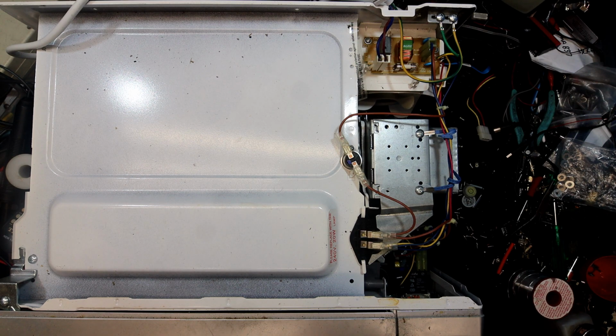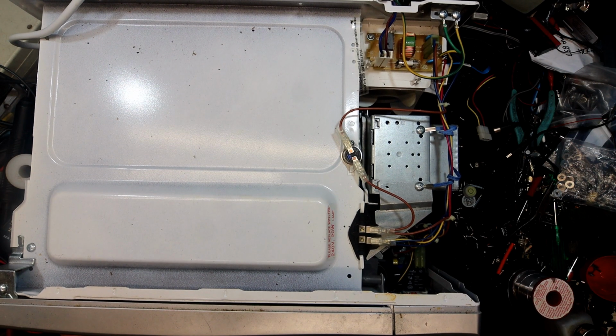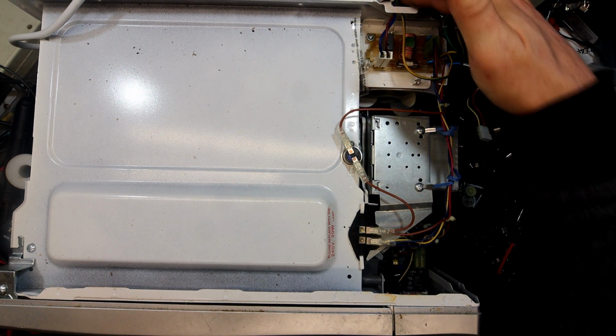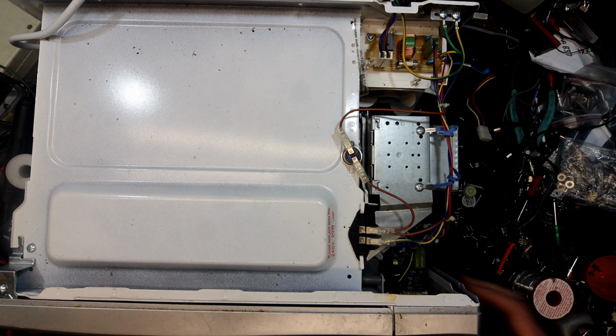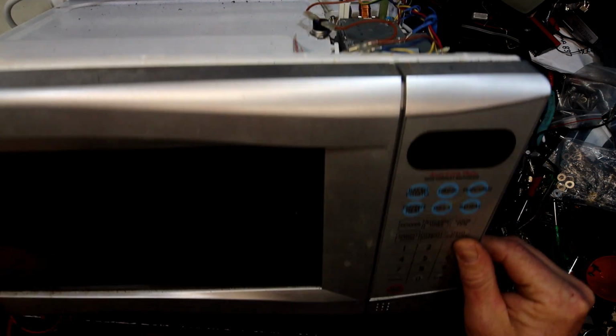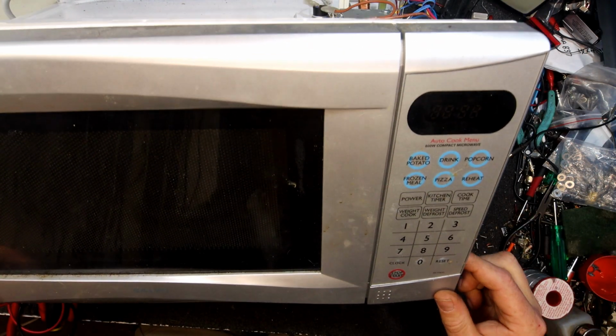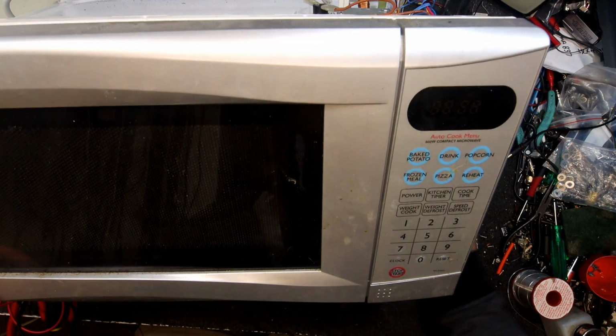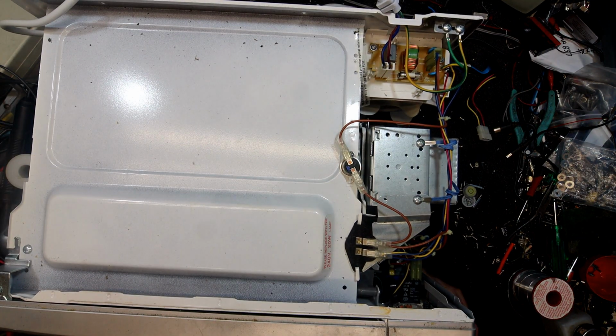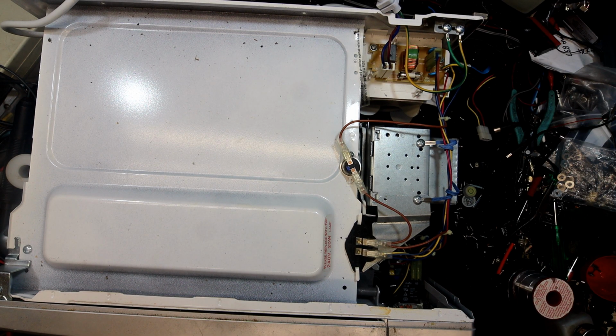The other hazard with these is, of course, they start at 240 volts. Everything in here, besides some of the stuff on the control board - the digital timer has a transformer on the back that steps it down, so that's lower voltage - but there's 240 volts all over the board because there's relays and stuff there, feeding 240 volts into the transformer.